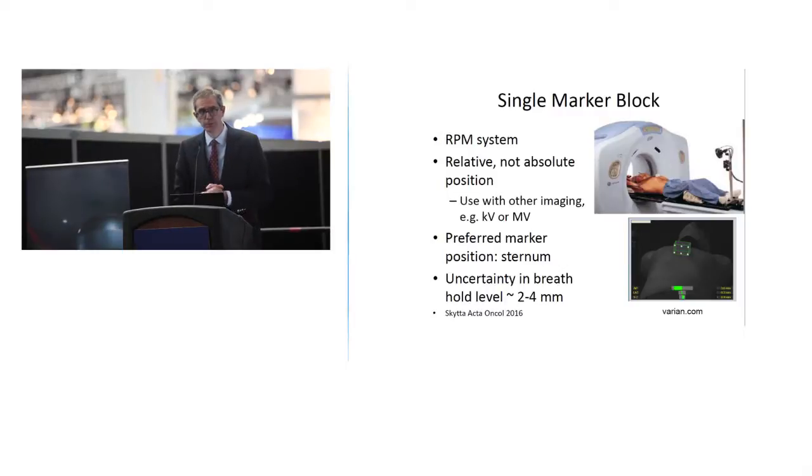I'm sure you're probably quite familiar with the single marker block or the RPM system. Here I'm showing this system in use in a CT simulator, and that is one of the major ways that we use this technology in terms of tracking the patient's surface while they're breathing during a CT scan in order to generate a 4D CT image. We can of course also use this for gating and triggering the beam, and for the application of breast I would refer to this as a relative type of positioning. In other words, you can visualize when the patient is taking their breath but it doesn't guide the setup of the patient within the room.